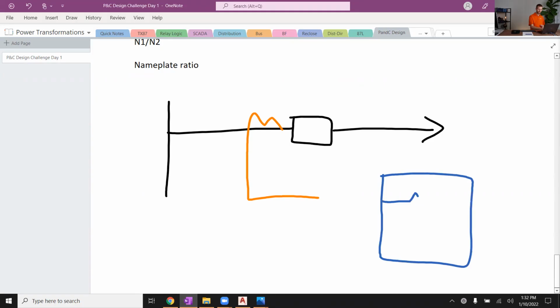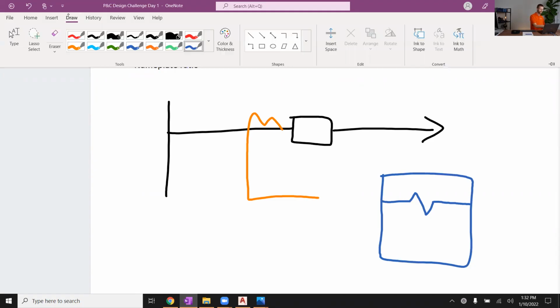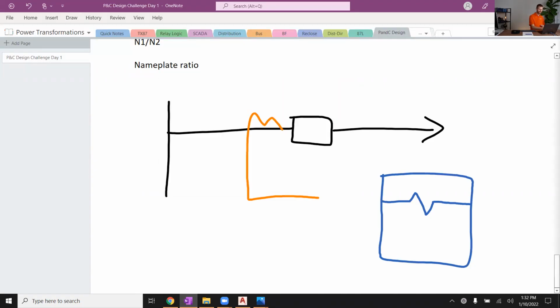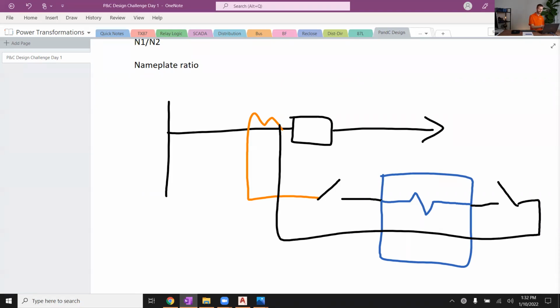In this case, I'm going to draw it a little more like we commonly do for a single phase. See if I can sketch this somewhat reasonably. This is going to be a test switch on either side of the relay. You know, we'd have our neutral that goes back around. I should have made that green perhaps, but the point is we've got this current terminal here.